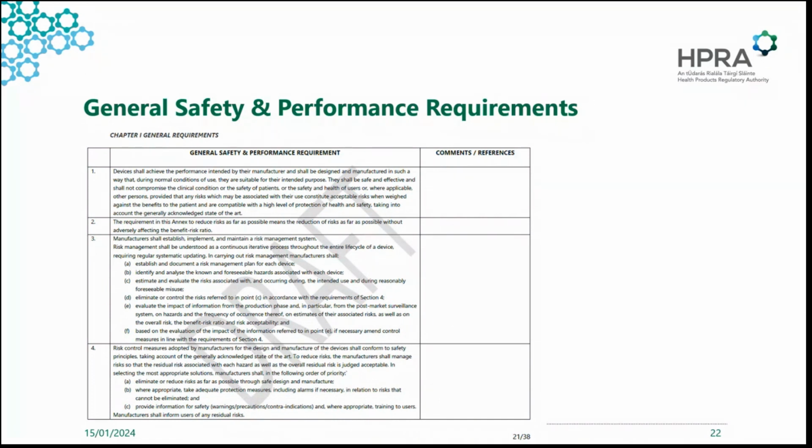So in principle, when you're looking through these requirements for a specific in-house device, you go through each of these requirements and see, well, do I meet that particular requirement? And what documentation do I have that supports that? Do I have documentation in my QMS system? Have I got validation data that can support that? And that'll enable you to essentially map where you have the evidence to support all those requirements. And that'll help you down the line when it comes to meeting some of the other conditions of Article 5.5.